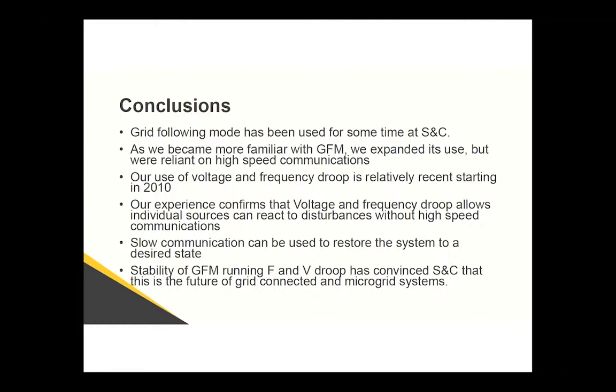We also make radio systems, and that's a major problem for our customers when the radios go down or are intermittent. So we really wanted a system that was insensitive to that communication speed. So overall, we think that using more grid forming inverters is the way to go, and we are firm believers in frequency and voltage droop. So, thank you.